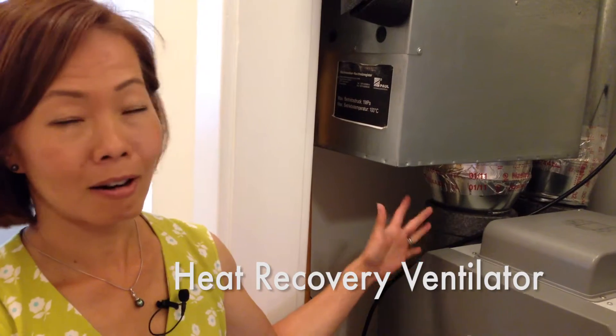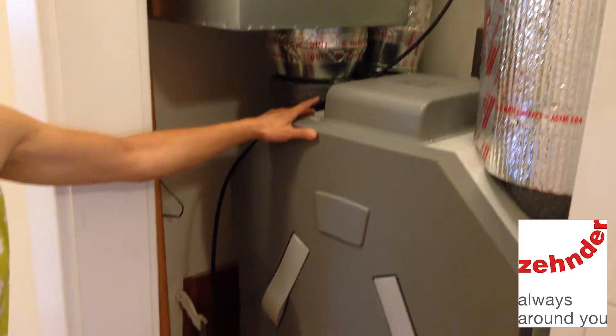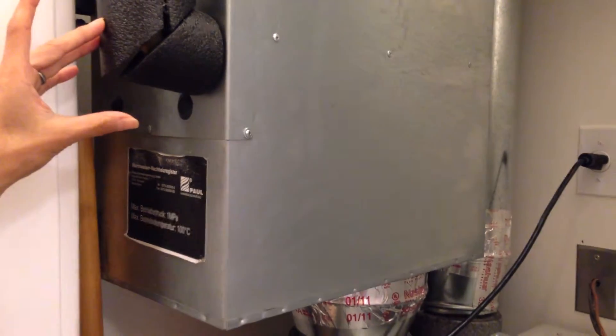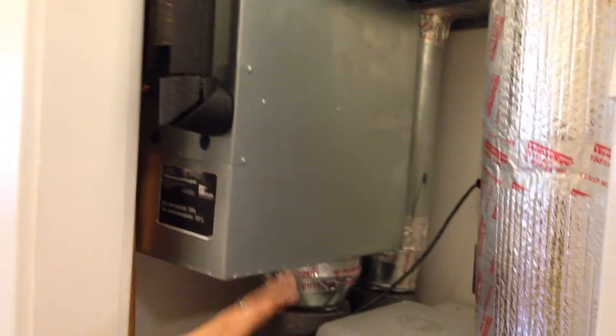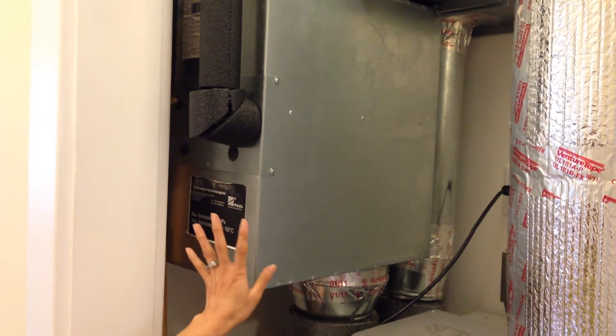This is the heart of our system — it's our lungs and also the way we get heat in the house. This is the heat recovery ventilator from Zehnder, a ComfoAir 350. This box here is a hydronic coil, and in it is a pipe that comes from our hot water heater running 120-degree water through it, so that if the house is not warm enough, there's additional heat supply to the air going to the different rooms.